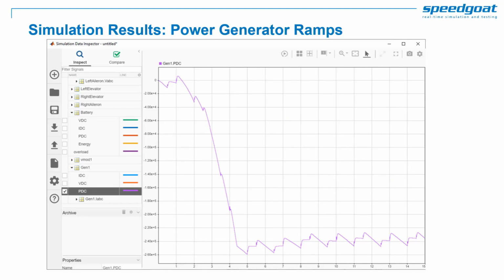We see generator power ramp to around 250 kilowatts. Negative means generated power in this case. In this scenario, we are ramping the power consumed by the electric turbines and have instructed the energy management system to use battery power when the generator reaches 250 kilowatts. So we are seeing the expected response here.